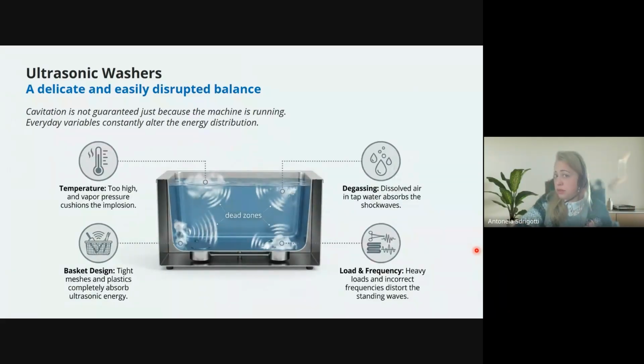So the first thing that we have to do when we change the solution of our ultrasonic washer is the degasification, okay? Because we have to make sure that we remove from the water all the trapped air that is normally within the liquid water, okay? So we have to eliminate this because it's competition between the air and the vacuum bubbles that we want to create, okay? So we will eliminate this air through normal air bubbles, okay? So we will see when we degas the solution the trapped air that will come out as air bubbles. This is the degasification. It is mandatory. Everyone should do this. When you put a new solution, you just have to run a degasification cycle, and then only after this, you put your load for washing.